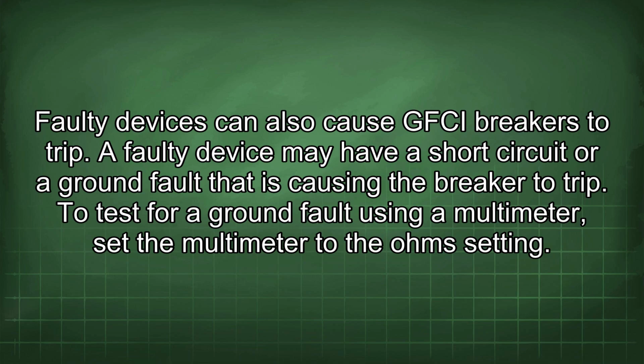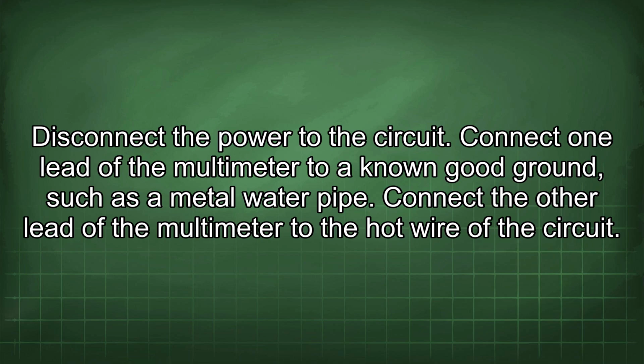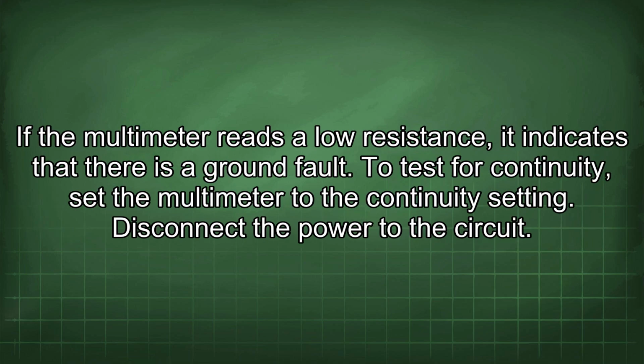To test for a ground fault using a multimeter, set the multimeter to the ohms setting. Disconnect the power to the circuit. Connect one lead of the multimeter to a known good ground, such as a metal water pipe. Connect the other lead of the multimeter to the hot wire of the circuit. If the multimeter reads a low resistance, it indicates that there is a ground fault.